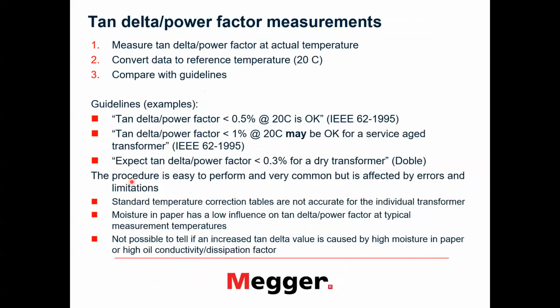Then we have tangent delta power factor measurements, which are also related to different moisture contents, of course. The higher the moisture content, the higher the power factor, the tangent delta, will be. How do you do this? You measure at actual temperature, you convert to reference temperature, and then you compare with guidelines. Regarding the guidelines, tangent delta below 0.5% at 20 degrees is fine according to IEEE. And according to IEEE, if it is below 1%, it may be okay for a service-aged transformer. And Doble says that if it is below 0.3, then it is a very dry transformer, and this is what you would expect for a transformer from the factory.